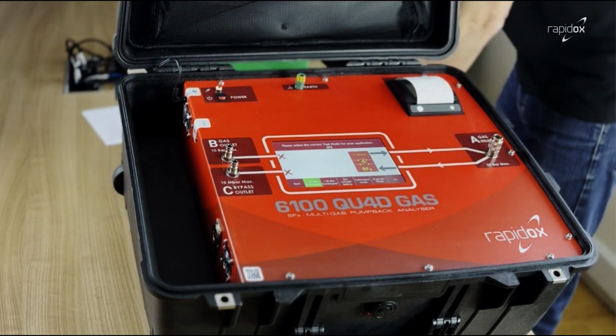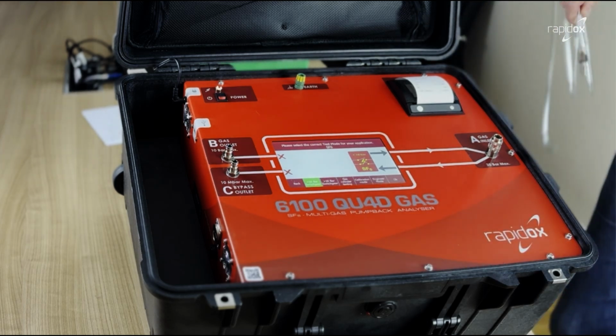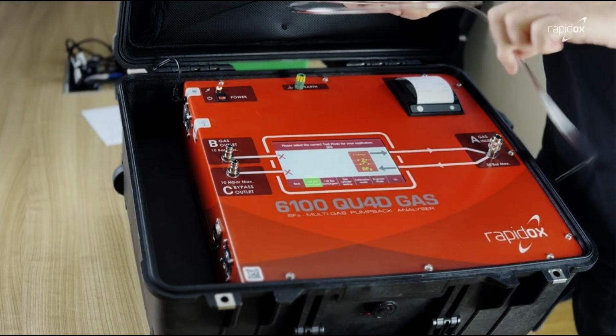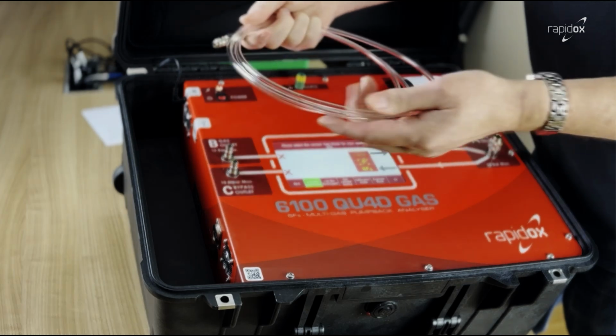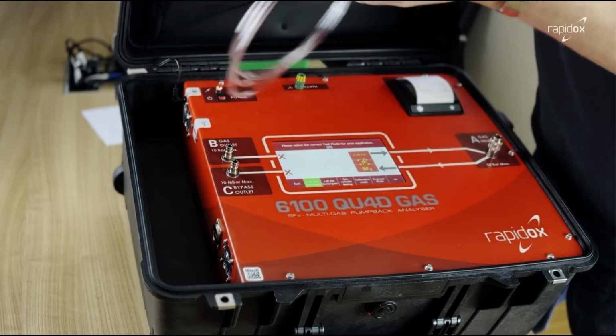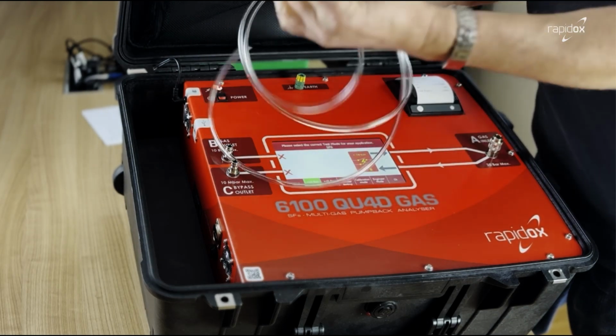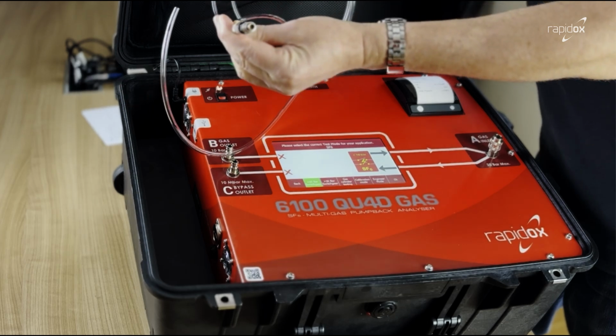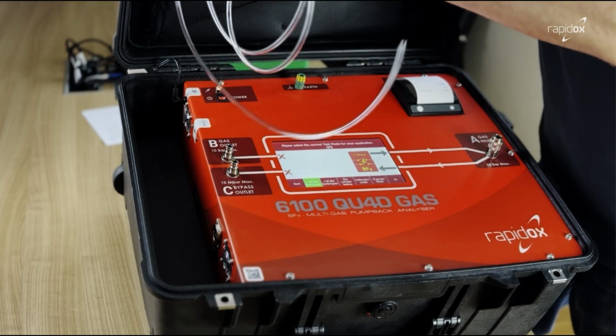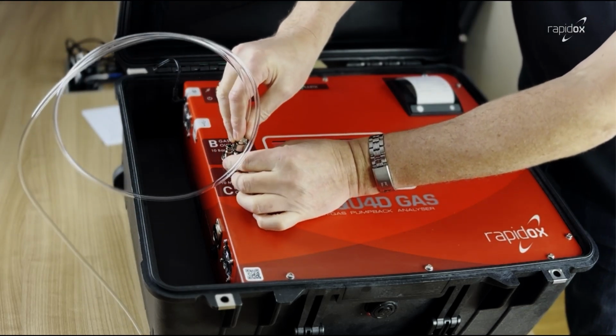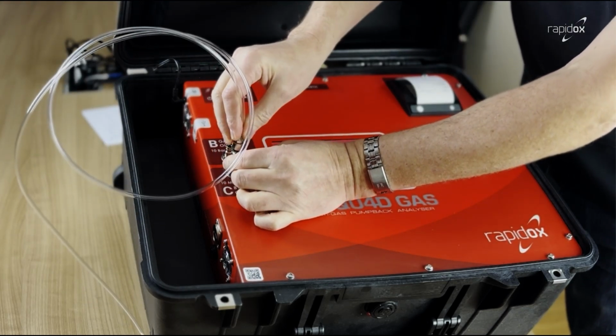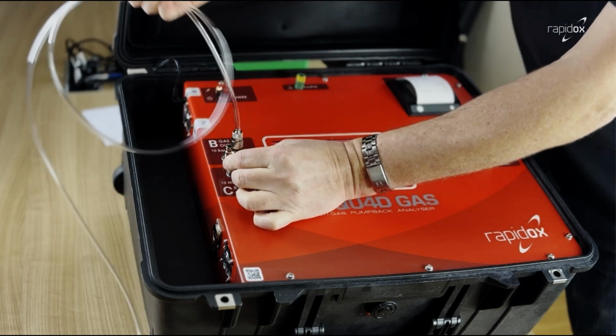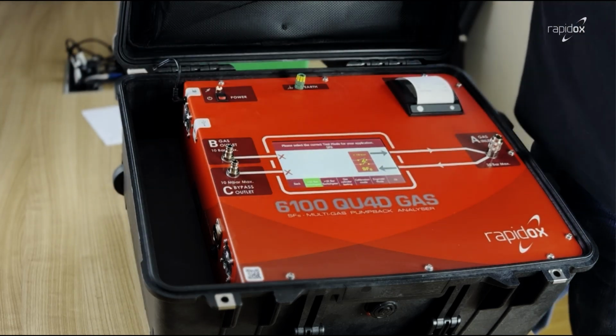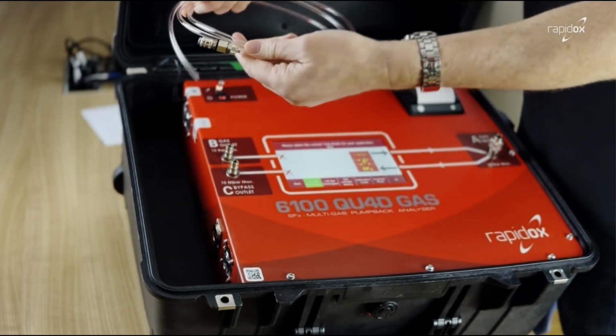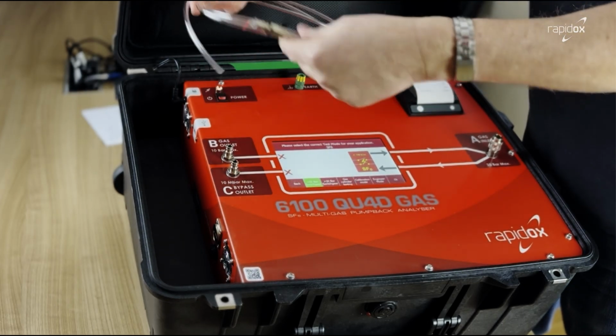Finally, we supply a tube and a connector for port C, which looks like this, polyurethane tube. And this one has a small Rectus series 20 female. And again, it attaches in exactly the same way onto the fitting here. And when this is attached, then you will be able to run gases such as nitrogen through it to do calibration of the dew point sensor.